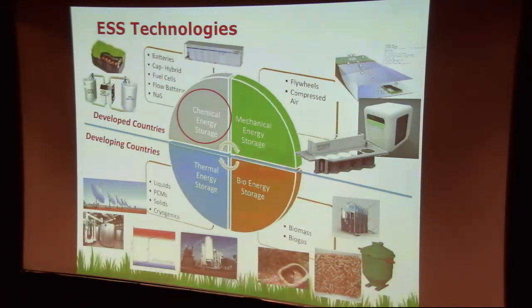We worked hard on this at Ontario Power Generation when we broke up Ontario Hydro. We couldn't fire biomass in the coal-fired station—Atikokan and others were destined for transfer to biomass, but the pellets were so poor in storage. Stored outside like a coal pile for a 60-70 megawatt station, they picked up humidity and became mush, making them useless to fire into the boiler, even though it was a tangential fired boiler, one of the best you can find.